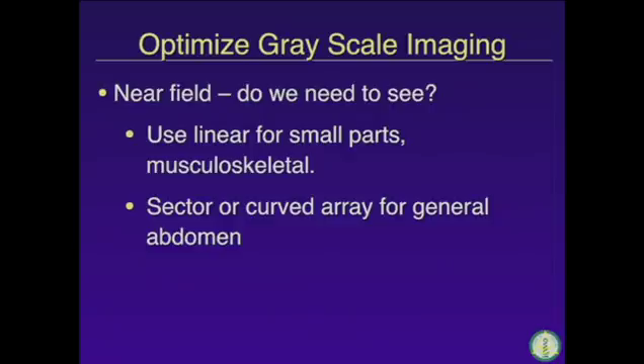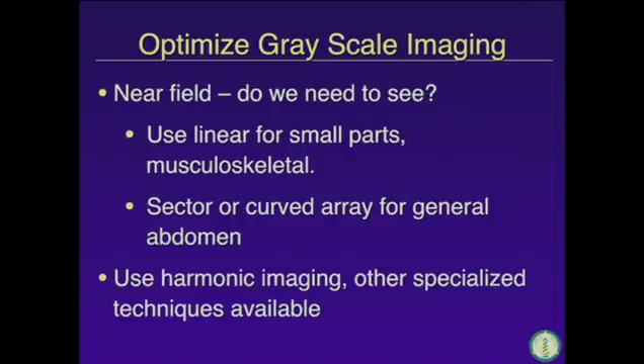So, the other thing you need to do once you've picked the transducer and it can image what you want to image is to determine which part of the body you need to image. Do you need to image the near field? If you need to see that, you're probably going to need to use a linear for small parts and musculoskeletal, and a curved or a sector array for general abdomen. And then if you still are having difficulty, you need to use harmonic imaging and the other specialized new techniques that are available.